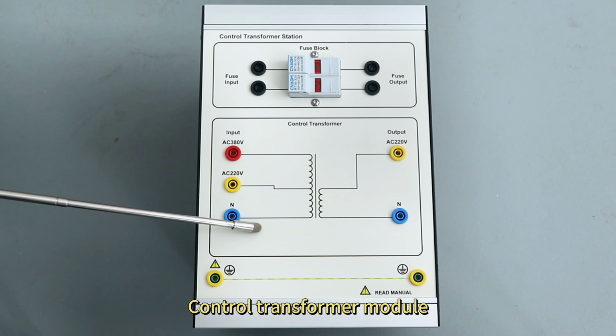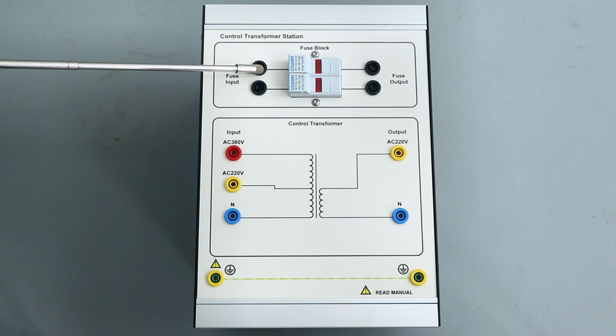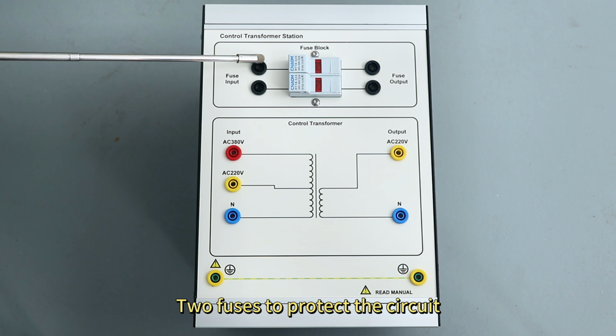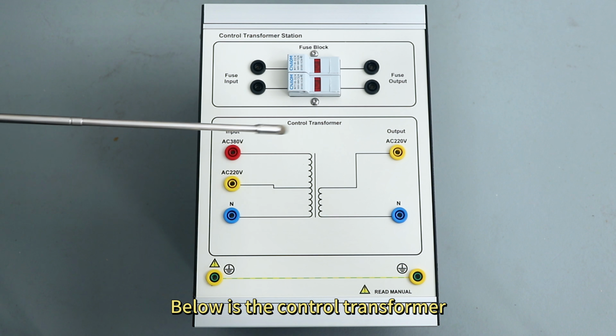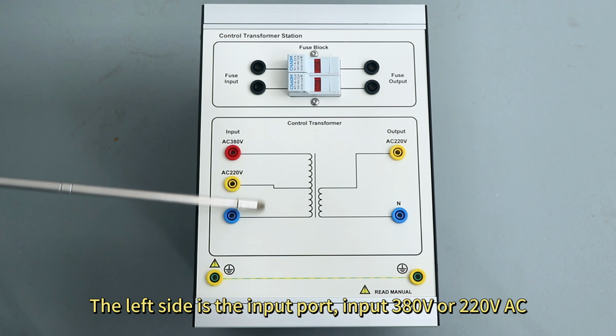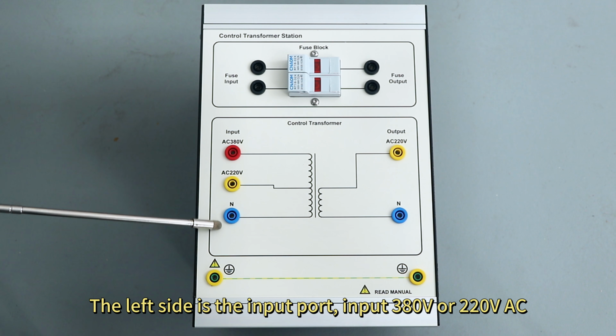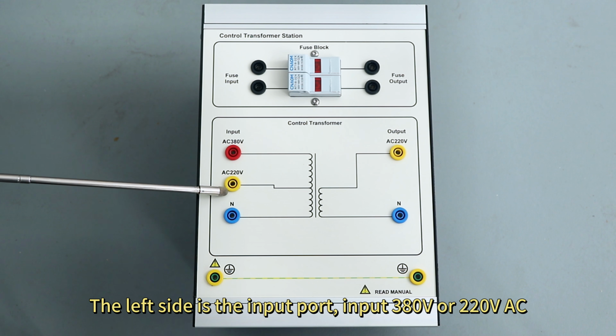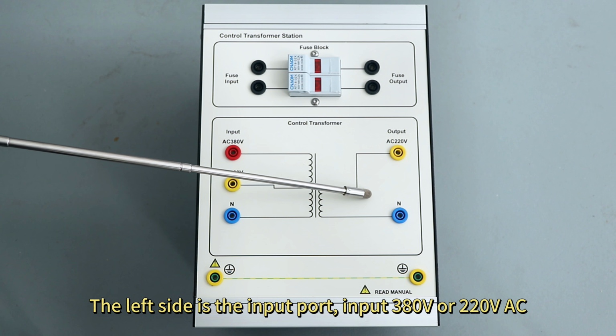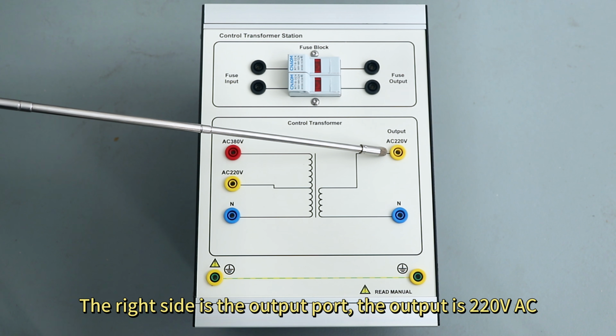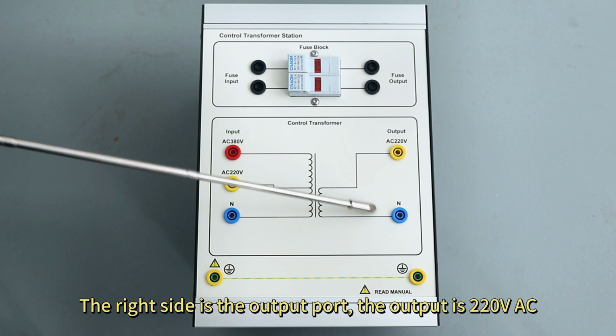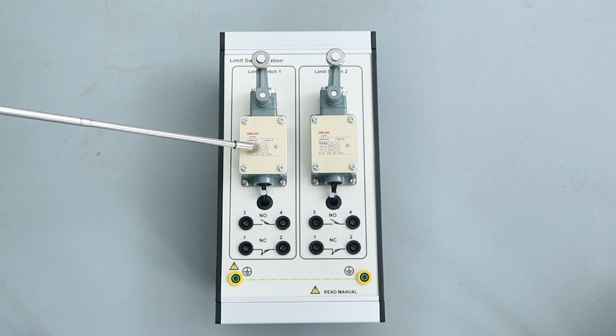Control transformer module. 2 fuses to protect the circuit. Below is the control transformer. The left side is the input port, input 380 volts or 220 volts AC. The right side is the output port. The output is 220 volts AC.